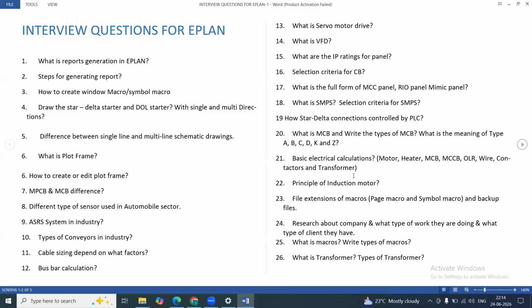I already explained these things in our classes. So first we have to find out the difference between MCB and MCCB. MCB is used for low rating purposes, while MCCB is used for higher amounts of rating. MCB or MCCB can be used in different types of devices, like inductive loads or resistive loads, in different types of loads. MPCB is especially used to provide protection in motors only. MPCB provides short circuit protection, overload protection, and phase failure protection - basically all types of protection that motors need. So MPCB is specifically used to provide protection in our motors only.